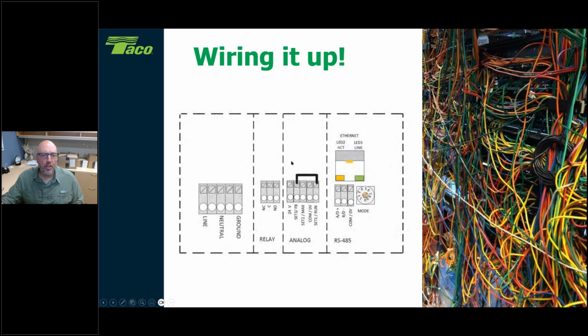The analog terminal block here, there will be a jumper defaulted in the circulator across set 1 and set 3, or the run terminal, which is why the circulator was running, because we have this jumper that's automatically installed for us. And then over here on the top right-hand side, you're going to see a Cat5 connection. The Cat5 connection here is for doing some advanced programming and monitoring of this circulator itself. We're going to address that in a little bit. And then we have this mode dial, which gives us a few other settings based upon how we use this terminal block.